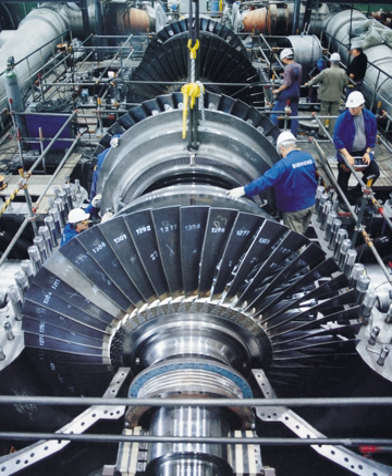Topic: Commercial power systems. Commercial power systems such as shopping centers or high-rise buildings are larger in scale than residential systems. Electrical designs for larger commercial systems are usually studied for load flow, short circuit fault levels, and voltage drop for steady-state loads and during starting of large motors. The objectives of the studies are to assure proper equipment and conductor sizing, and to coordinate protective devices so that minimal disruption is caused when a fault is cleared.